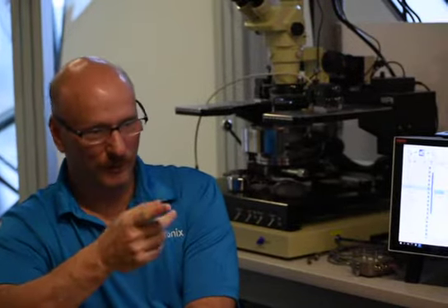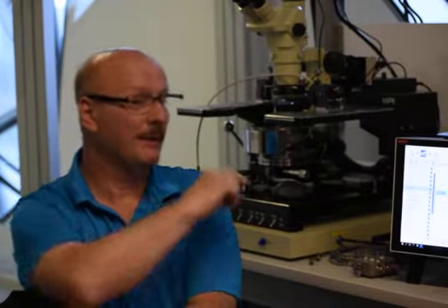So the reason I bring it up is because if we talk about upgrades, that's the time to upgrade. If you're going to send it in for calibration and you want to add a preamp, that's the time to do it, because there's a charge to upgrade, and with every upgrade comes a full calibration. So you can send this in, add a preamp, and you'll get a free calibration.